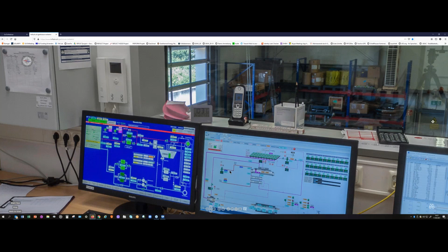And how does the installation affect the groundwater bodies? Do you also monitor this? Yes, of course, we monitor the groundwater level, so the reservoir, not the upper levels. We have a special sonic system where we constantly measure and control the level above the pump. This is a very important value, as it allows us to safely operate our brine pump, our production pump, so that we always have a top pressure on it.